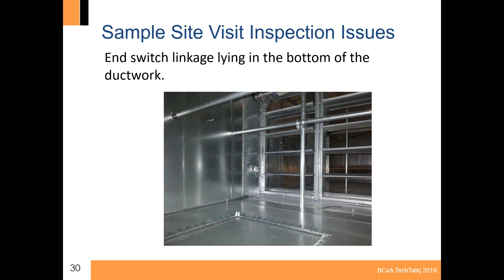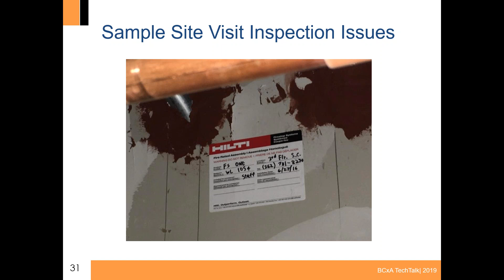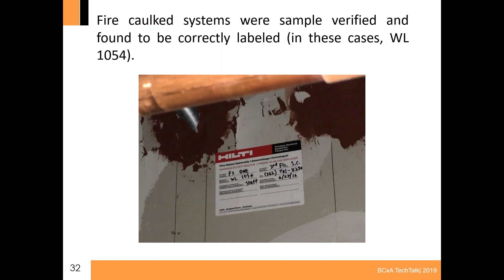Moving on from life safety dampers, we want to focus more on fire caulking. Here we have a tag, and what we often do is sample through, taking some tags to make sure they're appropriately labeled for the system. In this case, the tag was correctly labeled — you can see the WL1054 — that's what we're looking at.